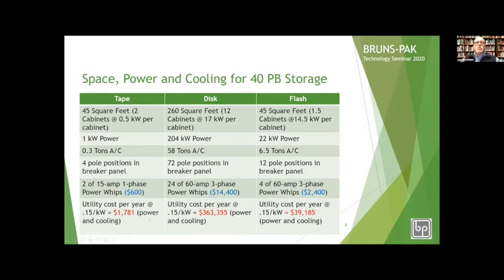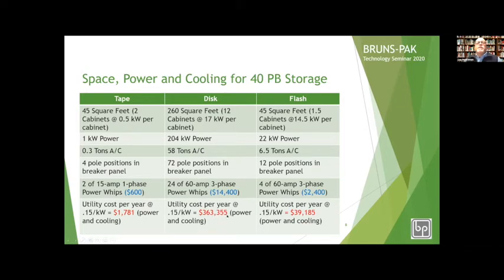What you'll see in the next comparison is a pretty major cost. At 15 cents a kilowatt — I live in Connecticut where we have very high costs — it's $1,781 a year to power the tape solution, $363,355 for disk, and just under $40,000 for flash storage. These numbers include not only the power to run the devices, but also the power to remove the heat the devices generate — both input power to the racks and the cooling for the exhaust coming off the racks. So there's a pretty phenomenal difference between the solutions.